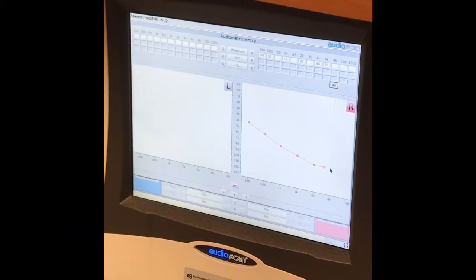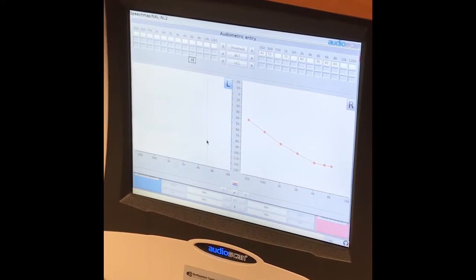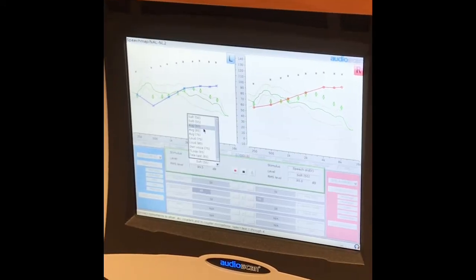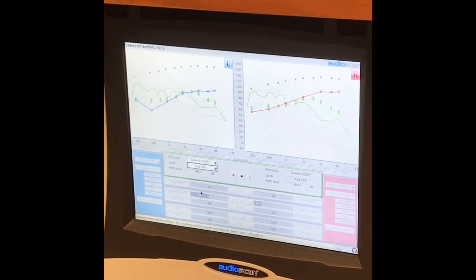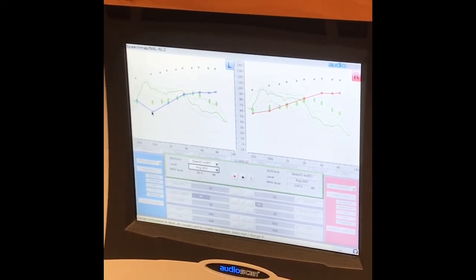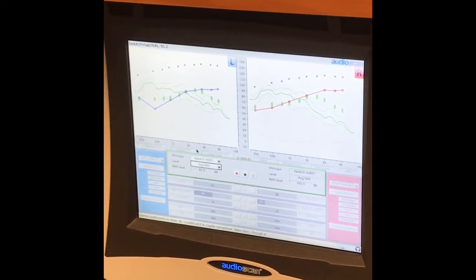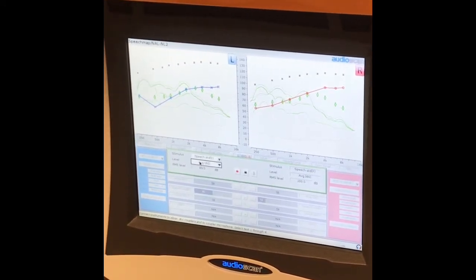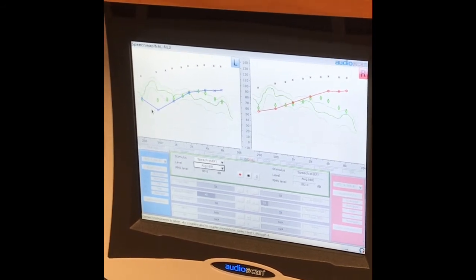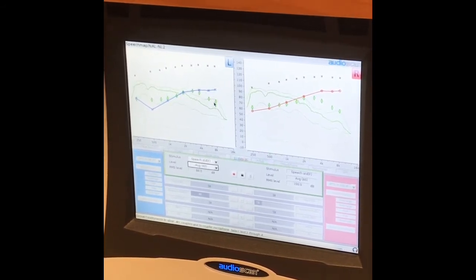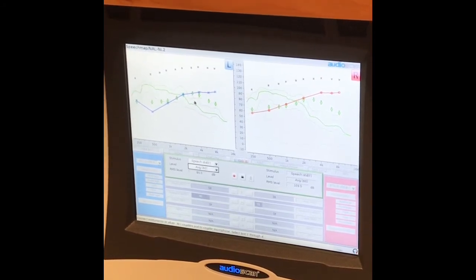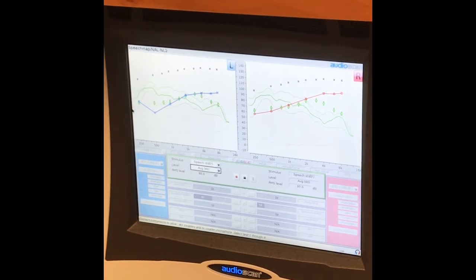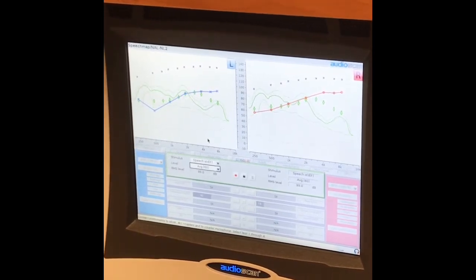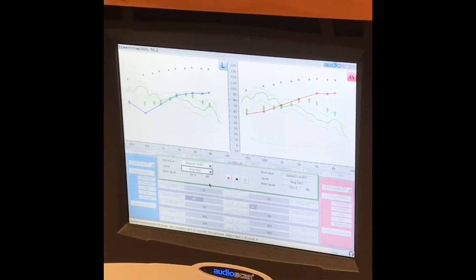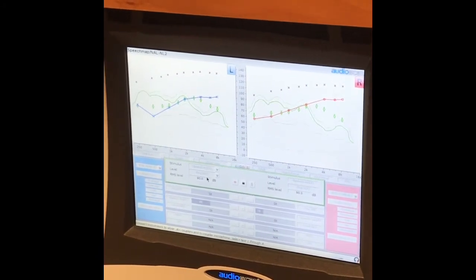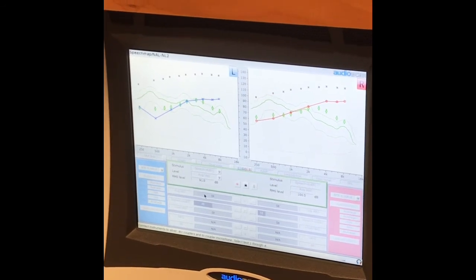So to start out, Esther is simulating a high frequency hearing loss in both ears. So the test box is producing live speech, and the hearing aids are interpreting the speech through the hearing loss that it was programmed to. The little stars all the way at the top, that is the estimated UCL for the patient. The blue line where the X's are, that is the hearing loss that we inputted. The green crosses are the target points that we are trying to reach, and the moving green line is the live speech that the hearing aid is hearing. So now Esther is pressing the record button, and this test is being run at an average of 60 dBs.